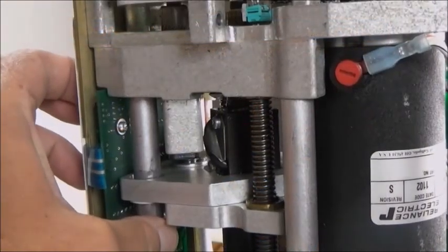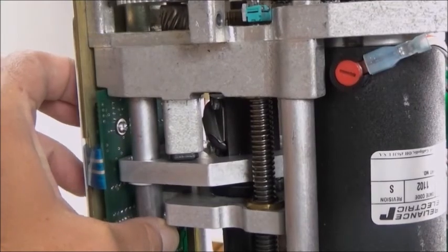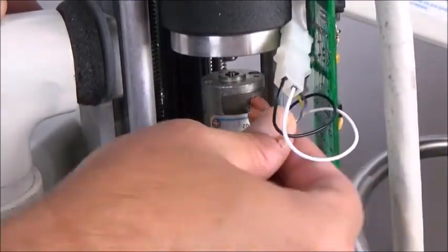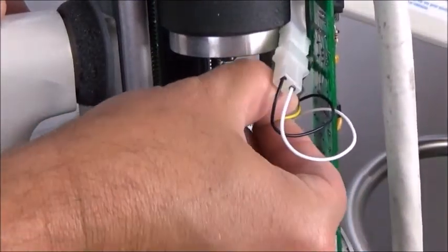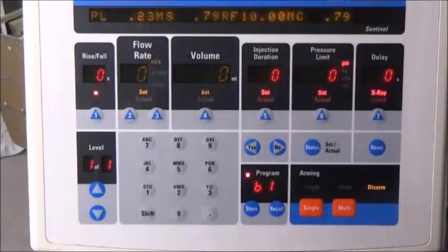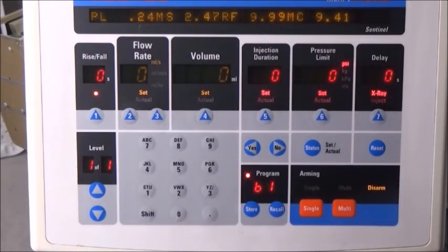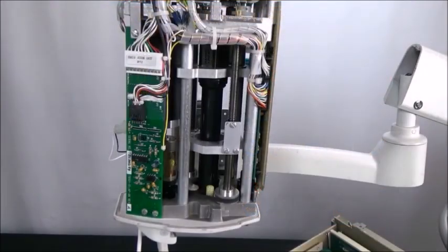When finished, fully reverse the piston and reconnect the MS motor lead. Then press the level down button on the display. This will reposition the MS plate back to its home position.